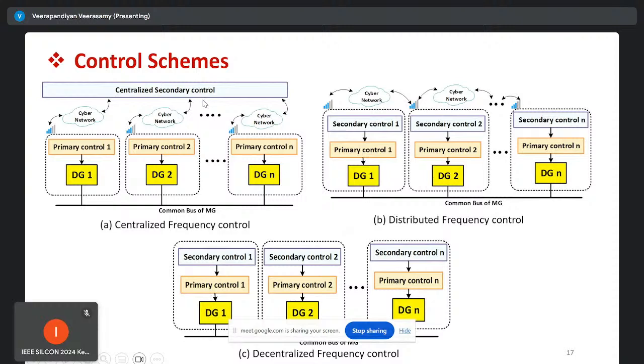This secondary control can be centralized, where there is a communication link to the primary controller. Alternatively, the secondary control can be distributed, where each distributed generation unit has its own primary and secondary controller, provided there is a communication link between each DG's secondary controller.